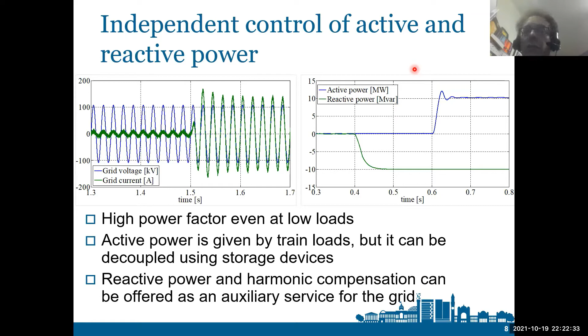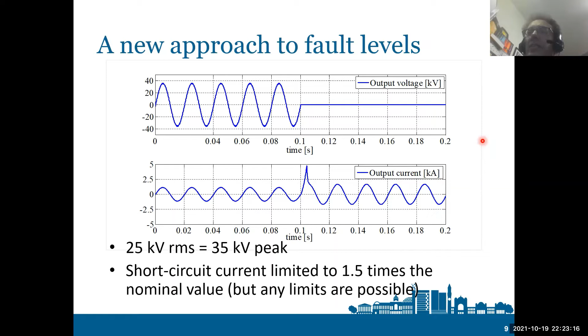The other important thing is the reduction of fault current because of the controlled nature of the converter. In this slide, I have presented what happens in case of a short circuit just at the output of the busbars of the converter. There you can see the current initially shoots up quite quickly, but then the converter control enables reducing the current to a value which is not much bigger than the nominal current, in this case just 50% bigger, and that helps reduce the complexity of the switchgear compared to a traditional railway.